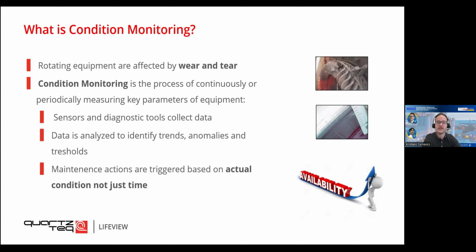So condition monitoring essentially is like a doctor that can monitor the health of the machine continuously. So either we do a permanent installation and we monitor the health all the time, or we do periodic checkups, like you would go to a doctor and periodically check up on your health. So condition monitoring consists of sensors, first of all, that can capture the data, and tools that detect and collect this data. Afterwards, this data can be analyzed to identify trends, anomalies, and thresholds of how good the health is, how far we can actually go. And then the main advantage is that the maintenance of your rotating machines can depend on the condition. So if the condition is good, maybe the maintenance can be postponed. So essentially, we want to optimize the time spent on the machine being online and not being offline. And condition monitoring is a great tool to actually do that.